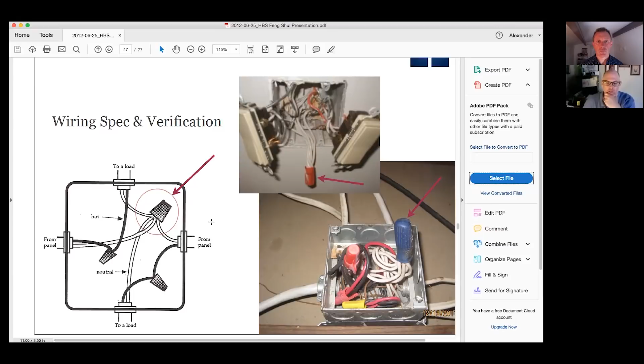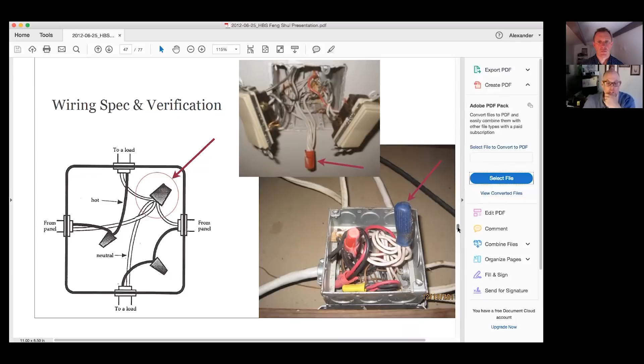The electrical inspectors for the city or county, or whoever is doing inspections, are not trained to look for this. Most electricians just think, if it works, what's the problem? But the problem is it creates stray current, and you no longer have that balanced load, which can create elevated magnetic fields throughout a building, similar to or worse than being right underneath a high voltage transmission line.